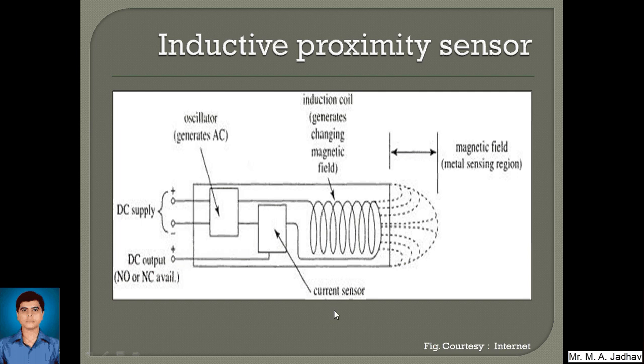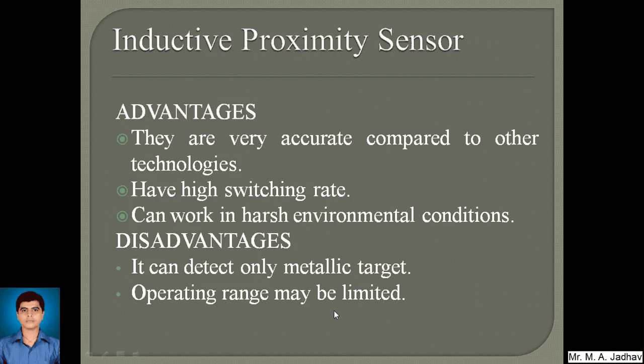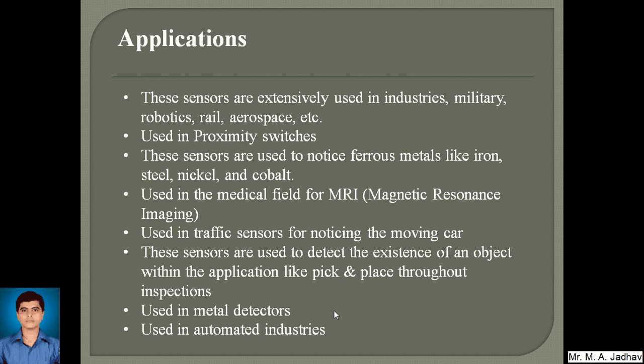The advantages of inductive proximity sensors are that they are very accurate compared to other technologies and have a high switching rate. They can work in harsh environmental conditions. A disadvantage is that they can detect only metallic targets — since we use a magnetic field, non-metallic objects or liquids cannot be detected. Another disadvantage is that the operating range is limited.